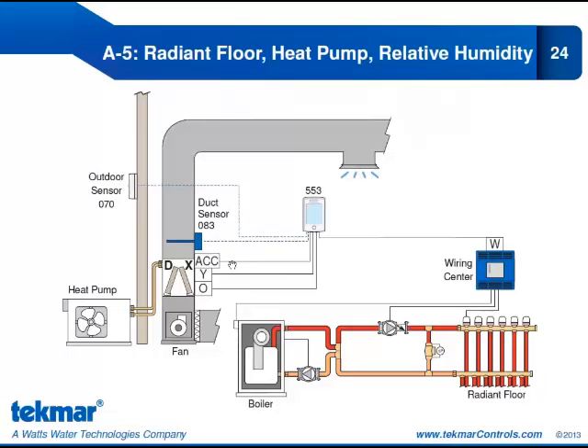Our accessory relay, in this case, will operate a dehumidifier. And we're going to be using the DX coil for dehumidification. So we talked about that earlier. The duct sensor 083 is optional in this case to provide freeze protection for the coil. Notice there is no G relay in operation because we're using the O relay for the reversing valve.